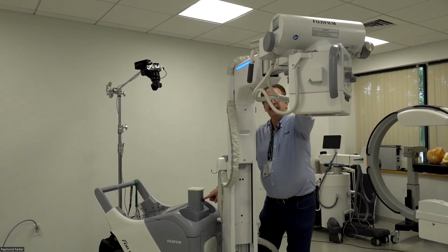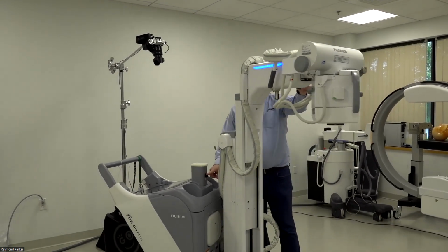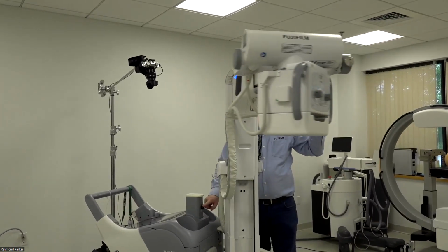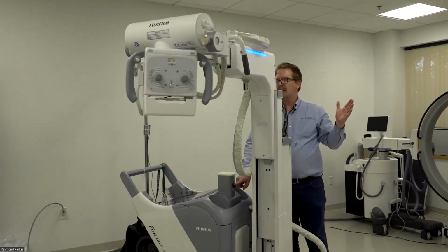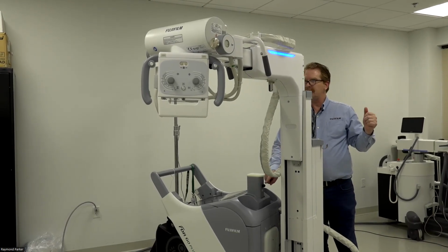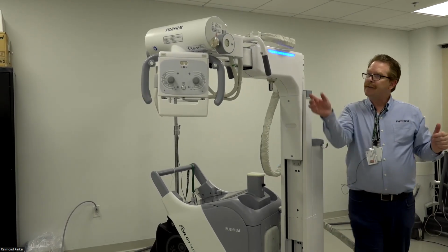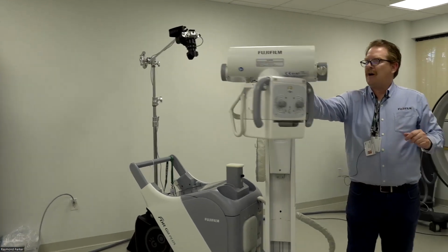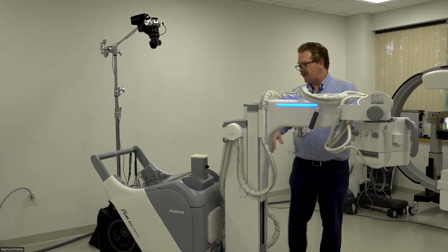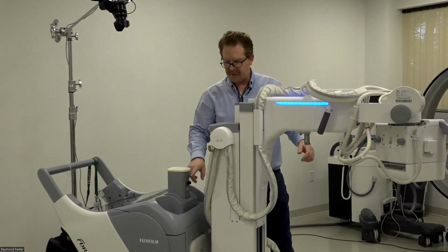So when working in a sterile environment, or an environment where the technologist doesn't want to lean on top of the patient, they can use this to work with their partner and then release the all lock release to engage the brake. Using a combination of those two can be very important for the ease of use and workflow of that technologist.